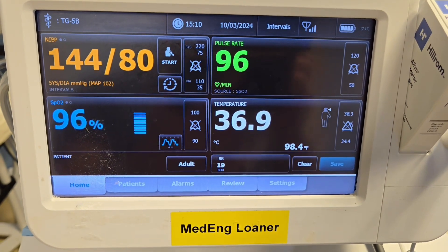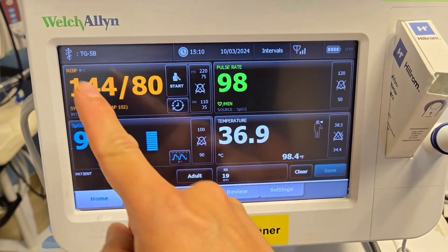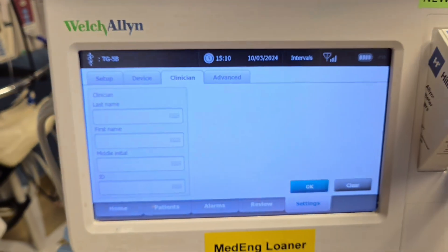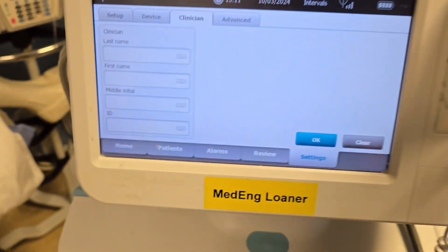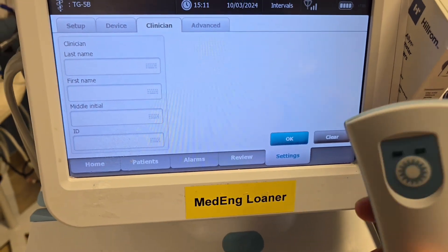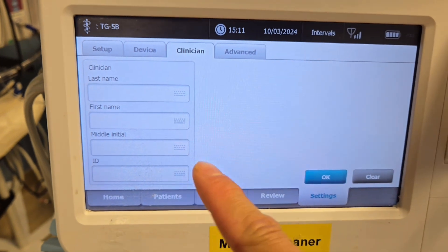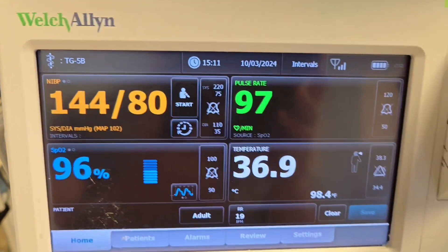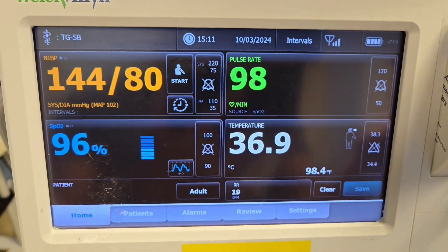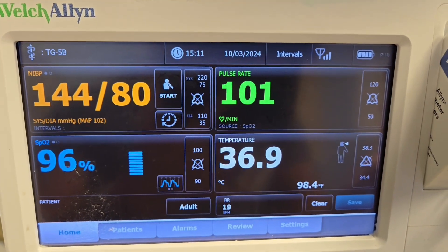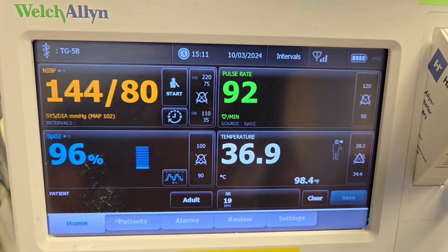Once you have printed out your clinician barcode, how do you scan that into the Welch Allyn machine? Very easy — just go to the top left corner where you see the little snake icon. Touch it and it will automatically take you to a window that says 'Clinician.' All you need to do is scan your barcode with the scanner. Once you scan your barcode, your clinician ID will pop up and you click OK. This logs your username with all the vitals for any patients. Each patient will need to be scanned individually so the data goes to the proper chart, but you don't need to re-scan your clinician barcode every single time — only once.